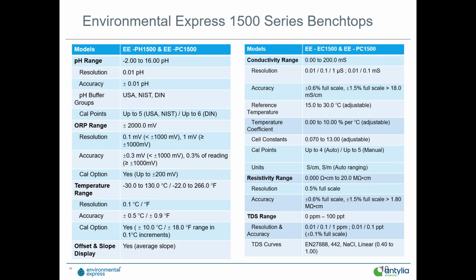Resistivity, for those folks who are measuring ultra pure water, kind of a cool parameter to use. Resistivity is just the inverse of conductivity. TDS 0 to 100 parts per thousand, good resolution and accuracy on that. The TDS curves included: EN 27888, a DIN ISO 7888 curve, sodium chloride curve, the 442 curve. Myron L made that famous. That simulates naturally occurring water. So that's going to be creeks, rivers, lakes. It's actually a 0.72, I believe, TDS factor, essentially. So the TDS factor is adjustable on those guys.